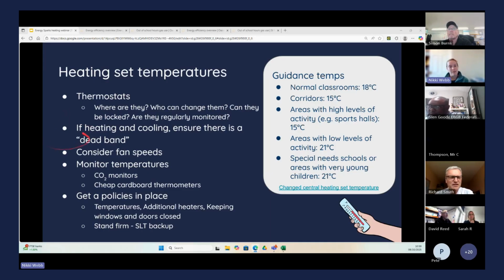As mentioned, if you heat to 18, and your school has heating and cooling or additional ventilation, make sure you're building in a dead band. You don't want to heat to 18 and then cool to 18, because cooling to 18 will feel cold. You heat up to 18, it stops, the bodies keep it warm for a bit, and cooling shouldn't kick in until 23 or 24. We've seen schools with separate heating and cooling systems working against each other at the same time, which isn't unheard of. I've even got pictures of aircon, heating, and windows open all at once, which is complete madness.